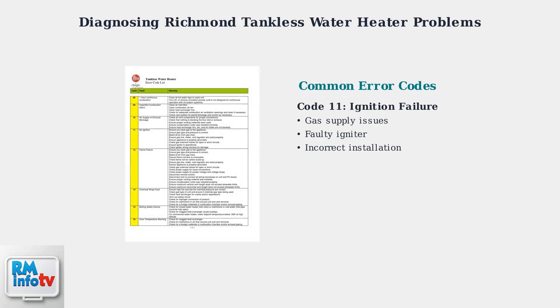Error codes provide specific information about what's wrong with your system. Code 11 indicates ignition failure, which can be caused by gas supply problems, a faulty igniter, or incorrect installation.